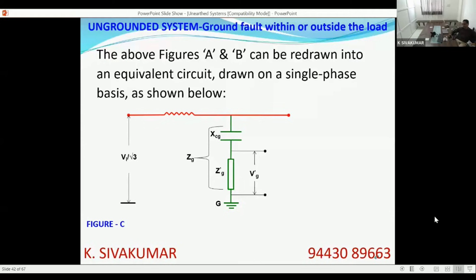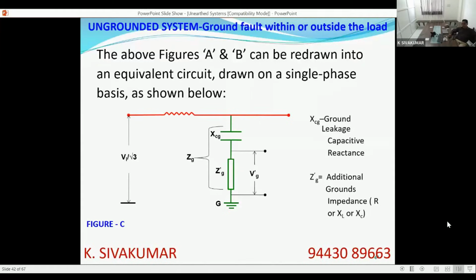So XCG is the ground capacitance. It may be XC R or XC Y or XC B. You can see this ZG is the total impedance, the sum of Z dash G plus XCG. Z dash G is the additional impedance introduced in the ground circuit during fault conditions. V dash G is the voltage developed across the external impedance. Now we have three possibilities: Z dash G is a resistive impedance, an inductive impedance, or a capacitive impedance. We will see what are the various transient over voltages developed under these three conditions.